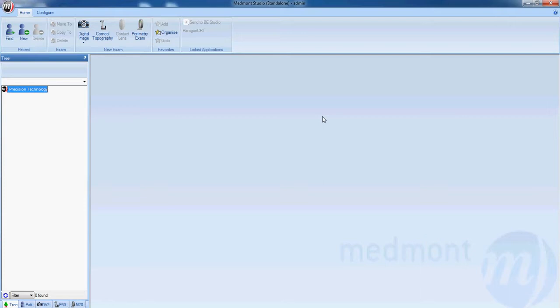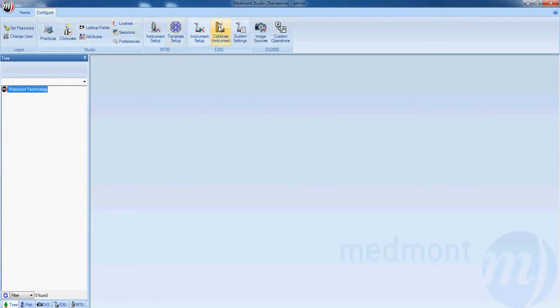Insert the narrow end of the device up and into the forehead rest, securing it with the screw going through the practitioner side of the forehead rest, through the hole and into the metal plate. Once it's firmly affixed, open up your Medmont software, select Configure, and Calibrate Instrument.